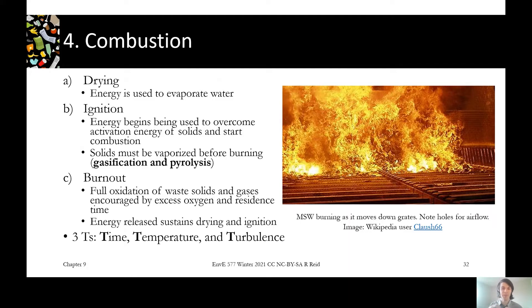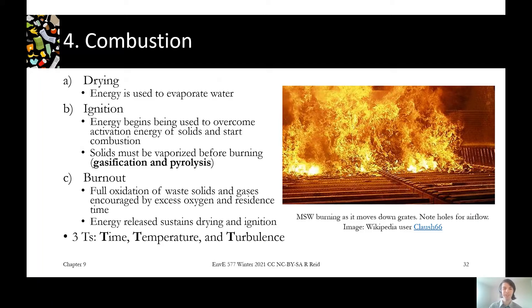All the solids first turn into flammable gases, liquids, and solids. A little oxygen moves them into flammable gases, and then more oxygen burns them out into carbon dioxide and other combustion products. That phase where everything burns out into final combustion products is called burnout, and the whole point of incineration is to achieve as much burnout as possible. The dimensions used to control this are known as the three Ts: time, temperature, and turbulence. There needs to be enough residence time, a high enough temperature for everything to volatilize, and enough turbulence for good mass transfer between solid and gas states.